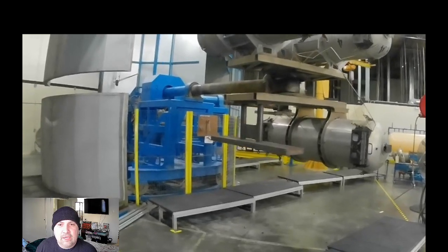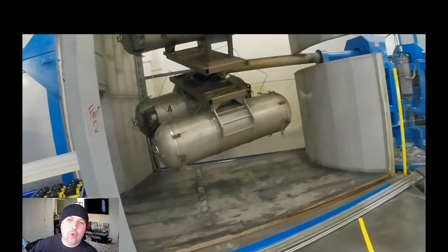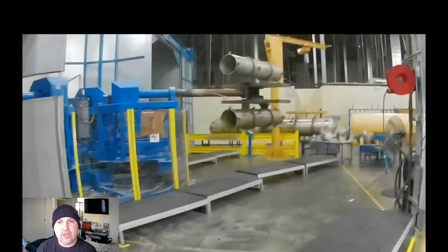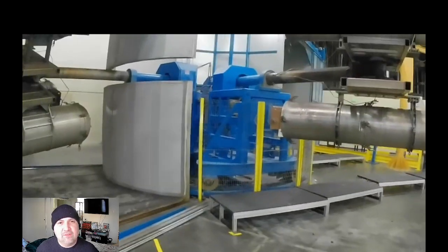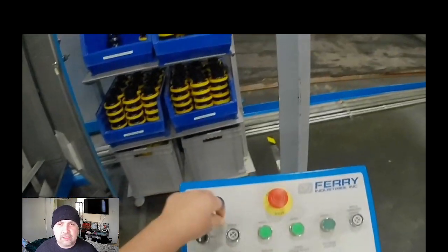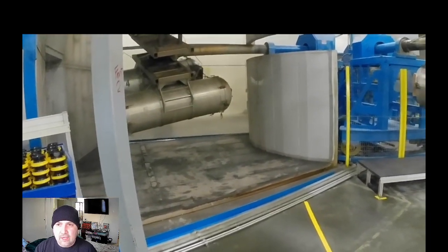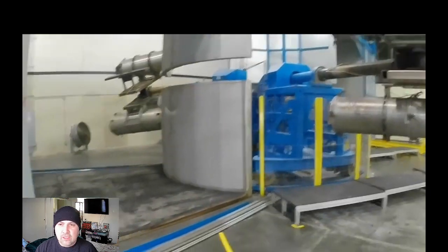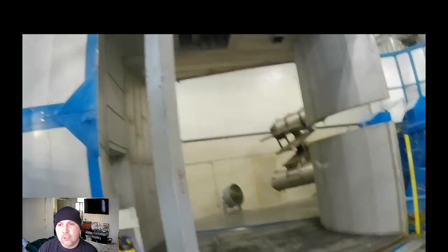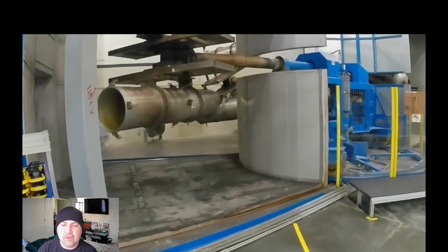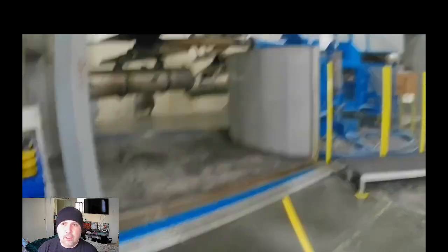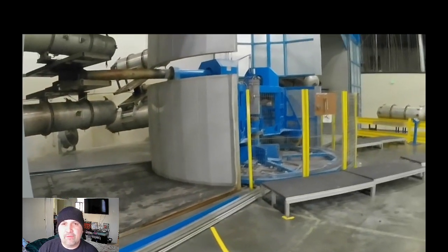So I'm rotating some of the arms, and I'm just kinda walking everything out of the way. On this piece of equipment, which is a very large piece of equipment, there are about 20 motors operating on it. So there's a whole bank of VFD drives on this. I mean, there are contactors galore, breakers, relays, and the rack, it has a double rack PLC. There's a lot going on in this piece of equipment. So it really took a lot to deep dive into this and figure out what was going on. I really couldn't go based off of what everybody had said prior. I had to just see for myself, but I kept everything in mind.